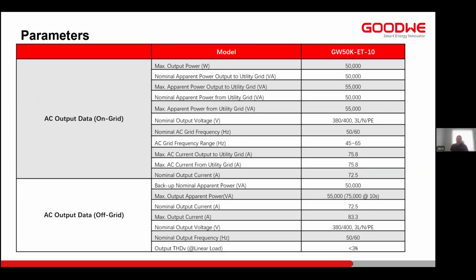Taking a look at the AC output characteristics. On the on-grid side, there's a maximum constant 55 kVA, so the unit can be constantly overloaded to 55 kilowatt. Also on the backup output, as mentioned, 75 kilowatts for 10 seconds, and that is to account for inrush currents or motor startup peaks, allowing the unit to run up to 10 seconds of overloading at 75 kilowatt.